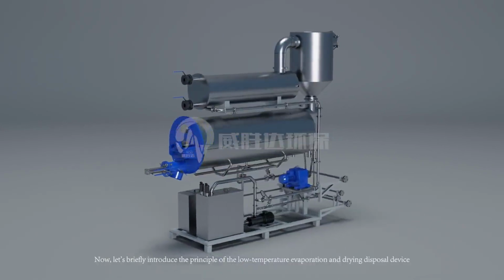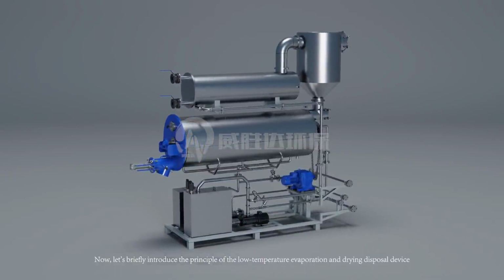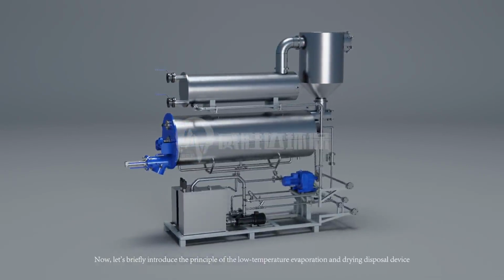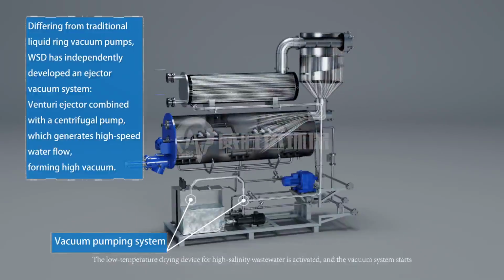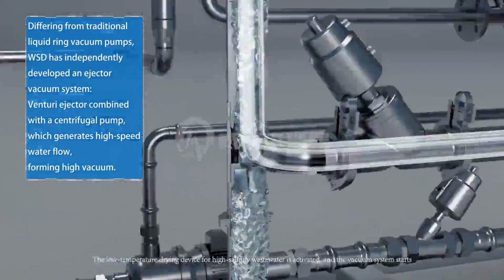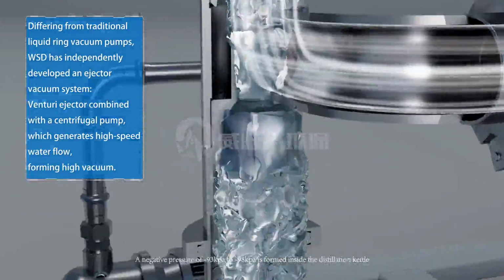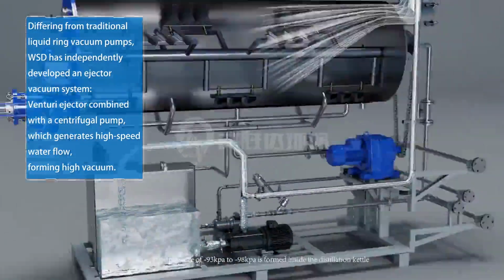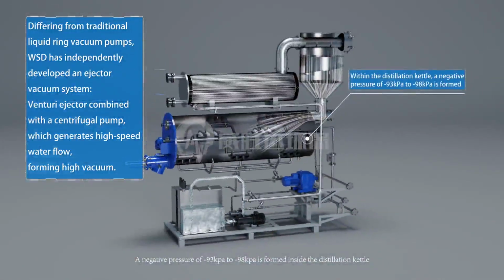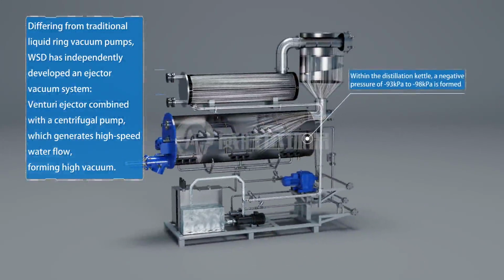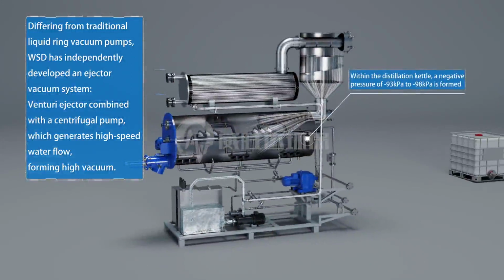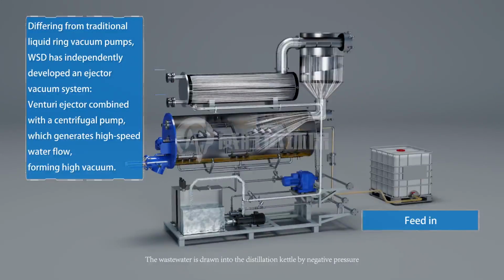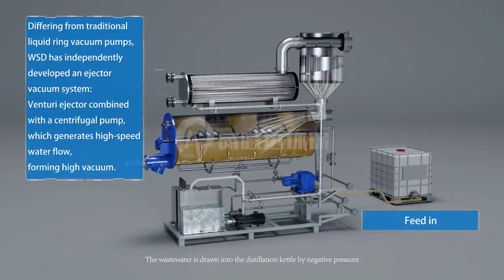Now, let's briefly introduce the principle of the low-temperature evaporation and drying disposal device. The low-temperature drying device for high-salinity wastewater is activated and the vacuum system starts. A negative pressure of -93 kPa to -98 kPa is formed inside the distillation kettle. The water is drawn into the distillation kettle by negative pressure.